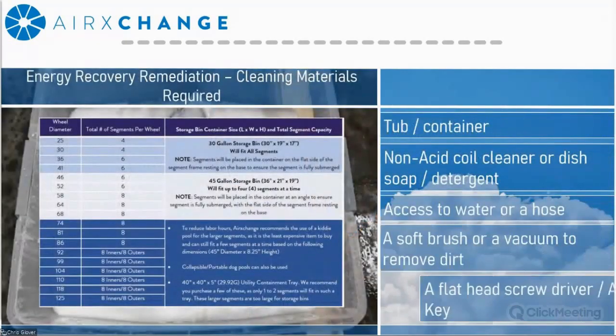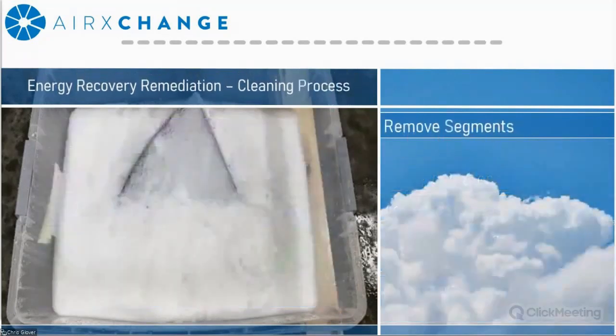So once the segment's removed, the additional materials that you're going to need are a large container or a tub. You can use that chart on the left to determine the relative size based upon the wheel diameter you may need. You're going to use a non-acid-based coil cleaner, or really any common soap or detergent. Dawn works great. You'll need access to water or a hose, a soft brush or a vacuum to remove any excess dirt, and a flathead screwdriver and an Allen key, depending upon size, to remove the segments. So it's not all that difficult.